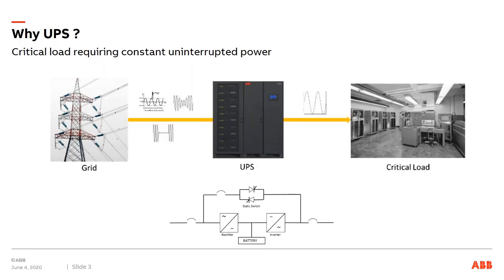So one more comment about the static switch, and there's a buzzword in the industry referred to as economy mode. Like any other electrical or electronic equipment, when you convert power, you create heat. There's heat loss. So in the online mode, going from the utility to the rectifier to the inverter and out, both the rectifier and the inverter have heat loss. It's not nearly as much today as it was a few decades ago. Modern UPSs are very highly efficient, but even in big UPSs there's still around 3% heat loss.